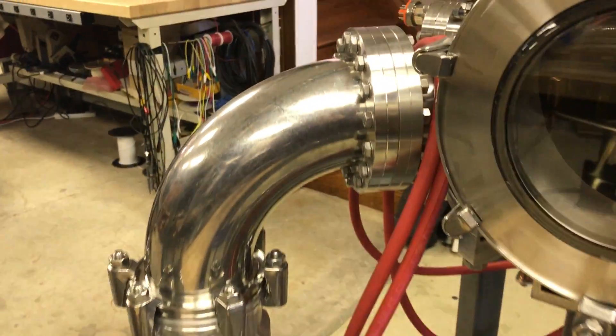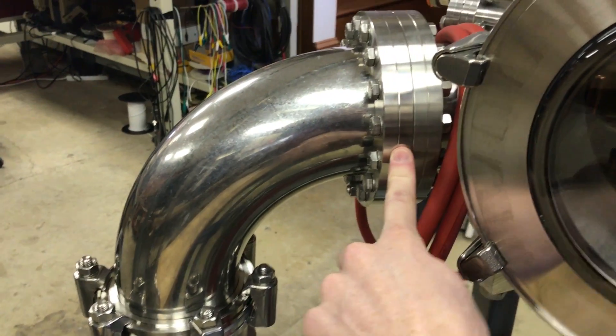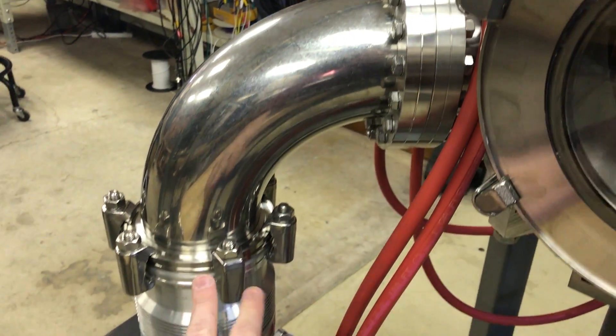My turbo pump here. It's a Varian navigator turbo pump. I have it mounted up on an elbow here. It's a custom Lesker part. This is a six inch conflat on this end. And then it goes to something called an ISO seal, which I'll talk about now.